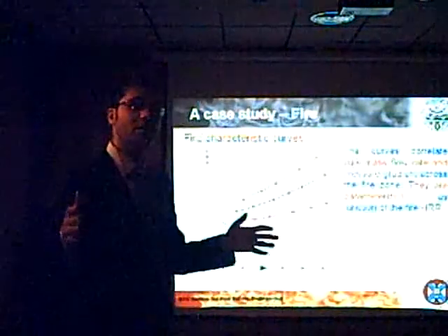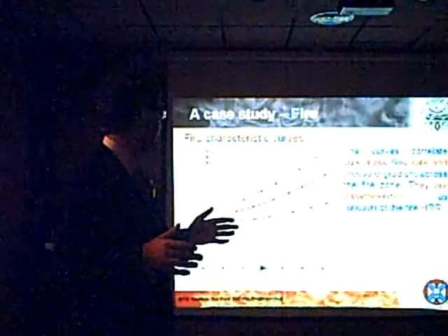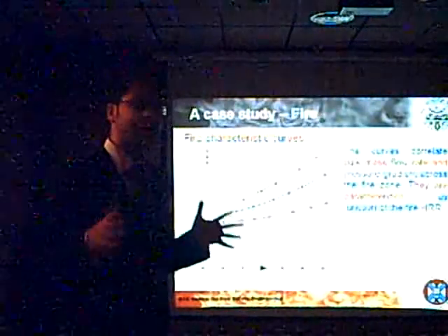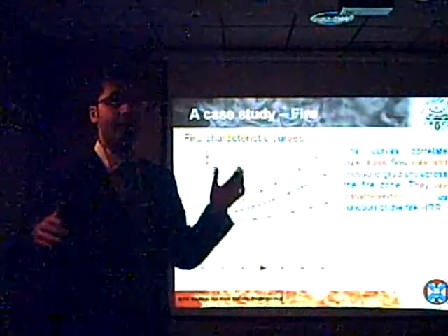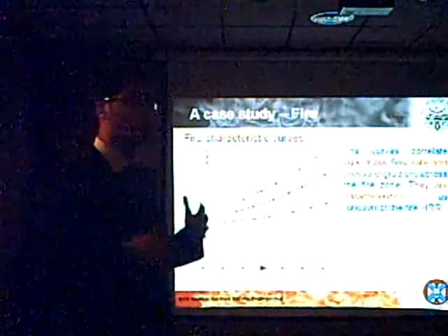So we took a domain which was 200 meters long, and we started making simulations varying the pressure boundary condition on both sides, and we recorded the mass flow rate through our domain. As you can see, the behavior of the fire within a tunnel is like an additional pressure loss the ventilation system has to fight against.